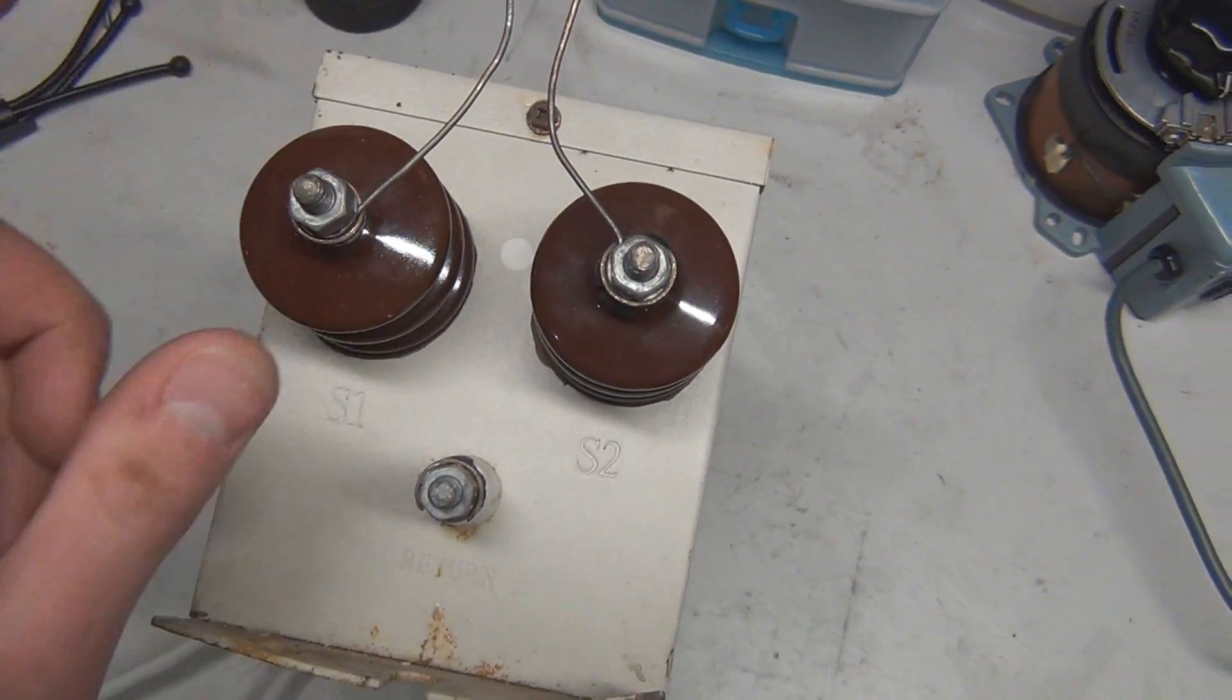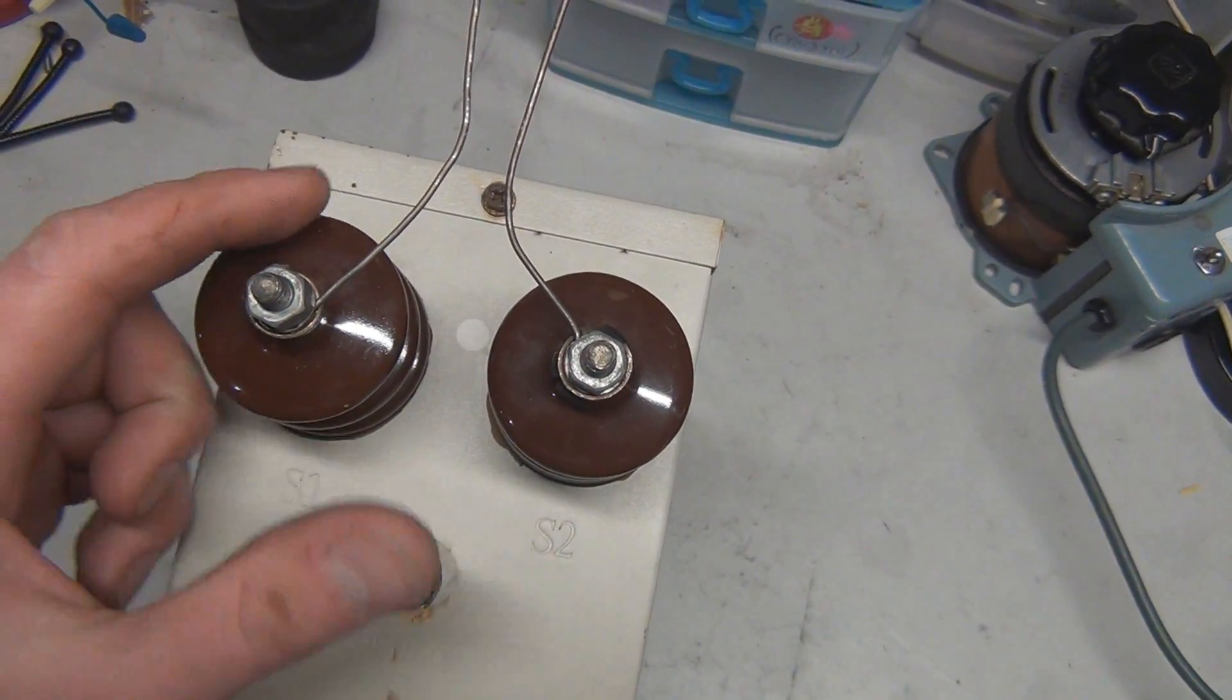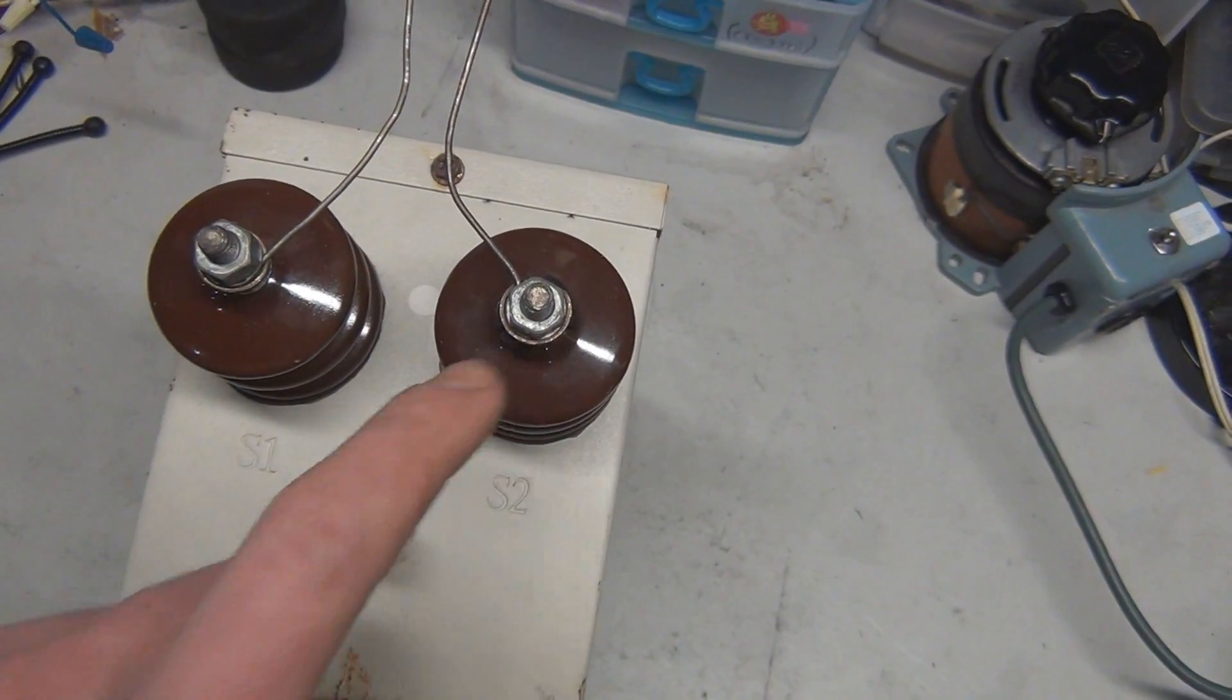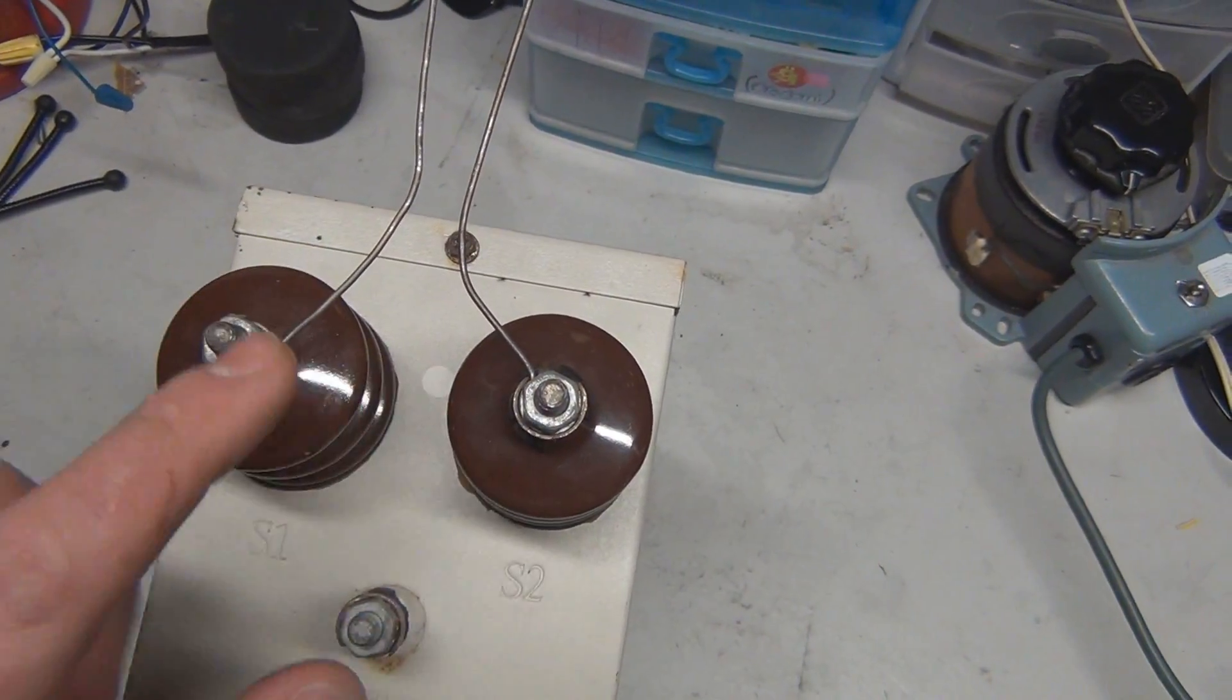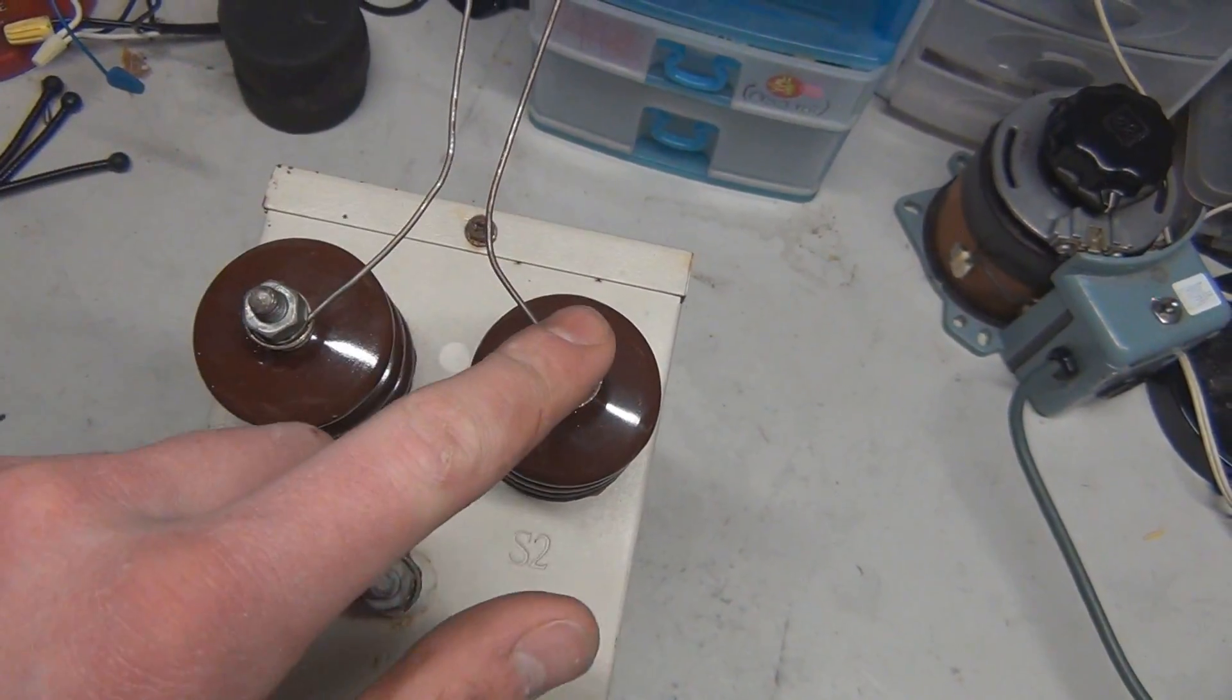So basically from here to here you have seven and a half kilovolts. From here to here you have seven and a half. And then because these are 180 degrees out of phase, both these give you 15 kilovolts between these two.